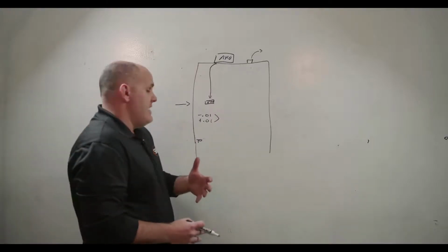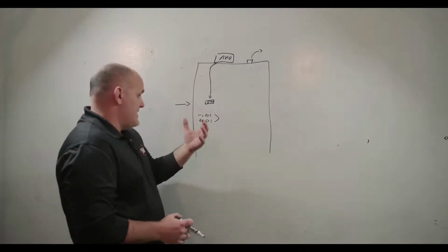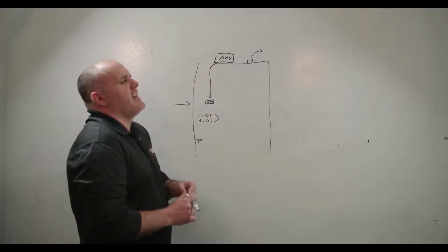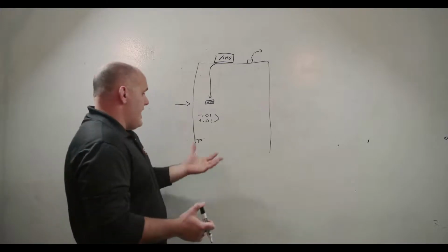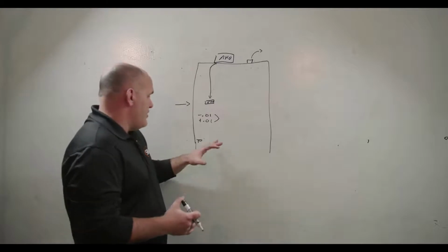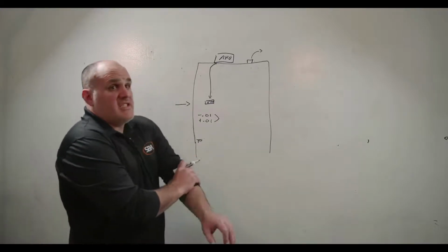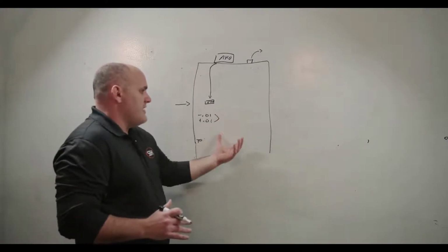We're going to have to account for the fact that as that door opens and closes, we're going to see a lot of noise in the signal. We're going to see it spike up and spike down artificially because of that door being there. So you can do that. Another scenario is to put building static in the plenum somewhere in the center of the building.